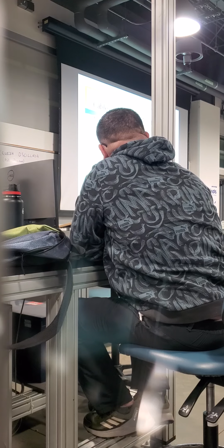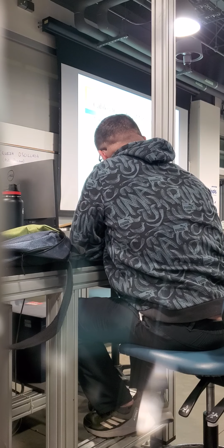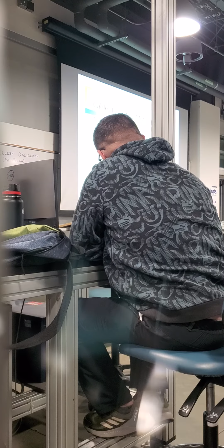Number 3, paper cables. We talked about the oil-impregnated paper. Paper alone is not a good insulator, but they found the magic in the secret sauce, the Krabby Patty formula. When you combine your paper with oil and you use various impregnation processes, like under vacuum, for example, you get a consistent distribution. It becomes an excellent insulator. And actually, we already have the teaser for the 268 transformer class. We see a lot of paper insulation in some of our transformer systems.